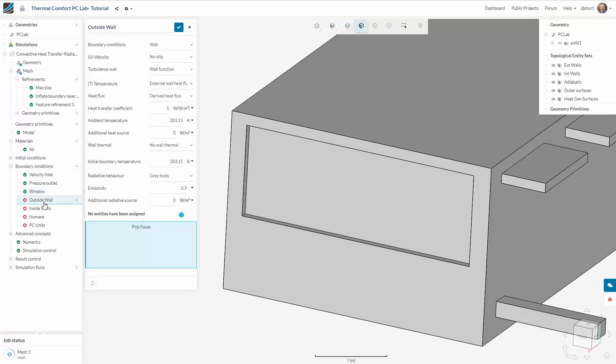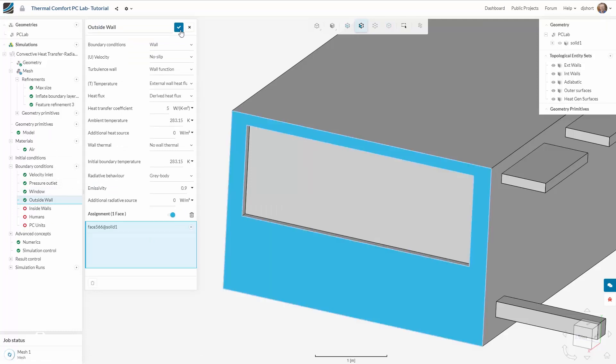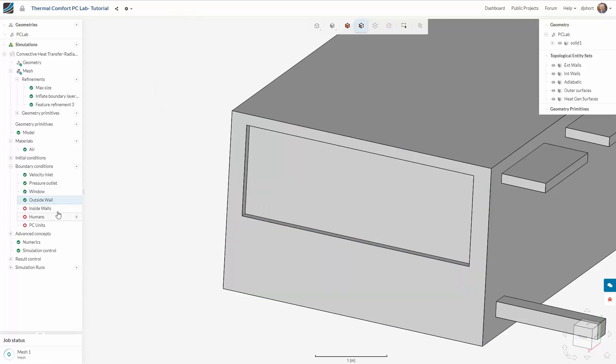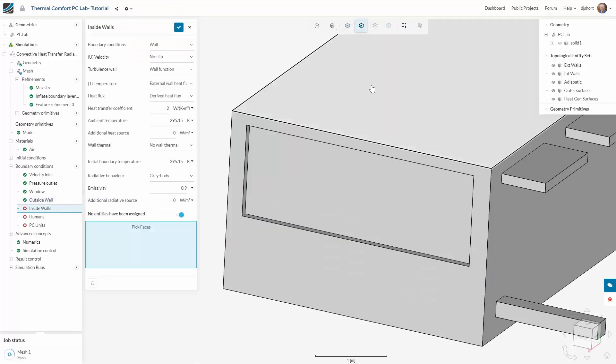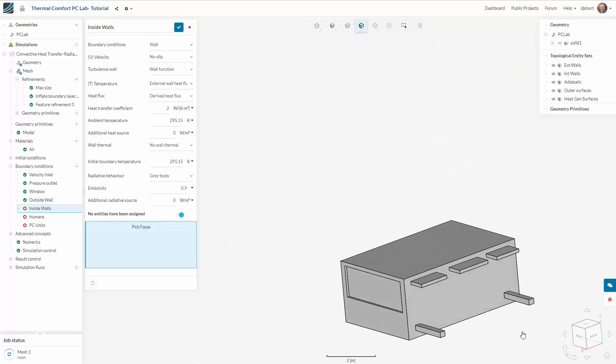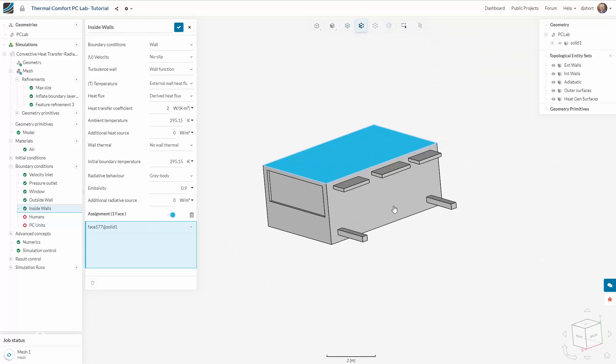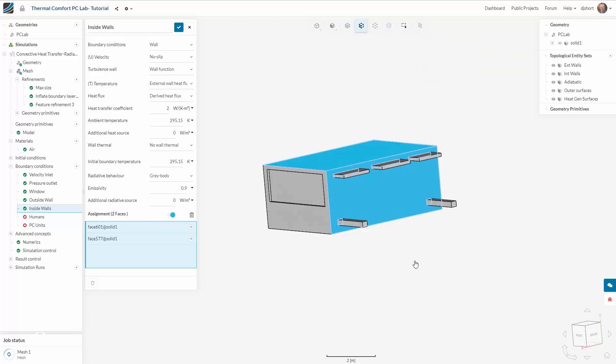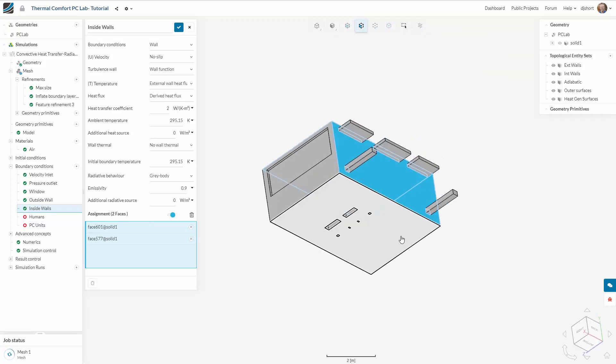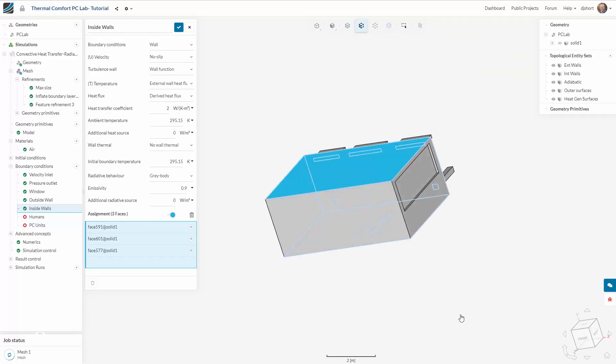Similarly for the outside wall I also give the external temperature plus a heat transfer coefficient. On the internal walls I use the internal temperature of neighbouring rooms plus a heat transfer coefficient.